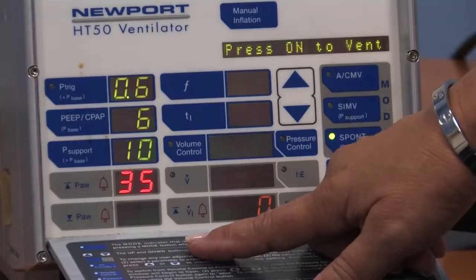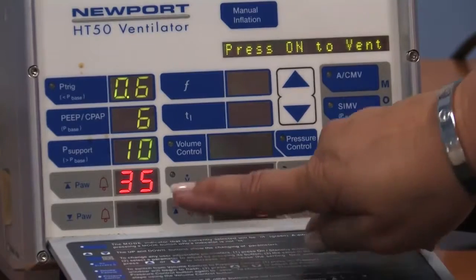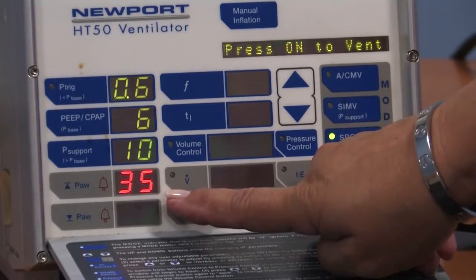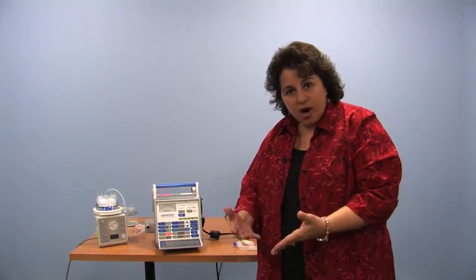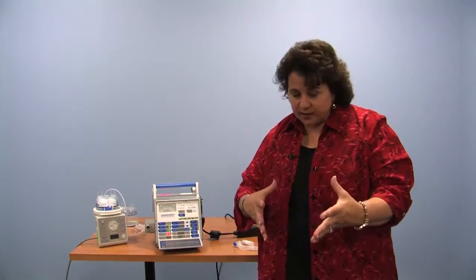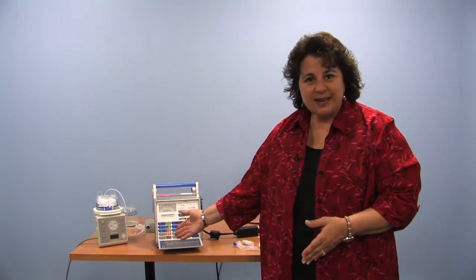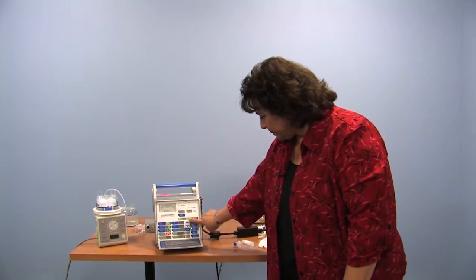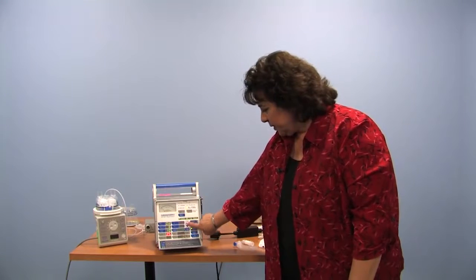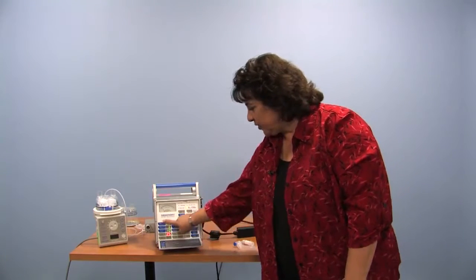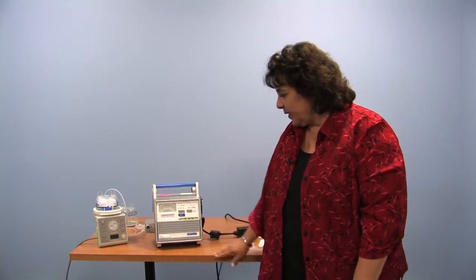You see this blank. It isn't because the machine doesn't care if it's disconnected. It's an internally set low pressure alarm. We don't choose it, the machine chooses it. We do, however, choose the high pressure alarm should there be a kink in the hoses, a cough, something in the circuitry that sends the pressure above 35 centimeters of water, or whatever is predetermined for your child with your family, your caregivers, your home nurses, your respiratory therapists, etc. For the purposes of today, I said 35. So those are the different modes, the way in which you set them, the way in which we choose different settings on the front of the machine. It would be like this running.